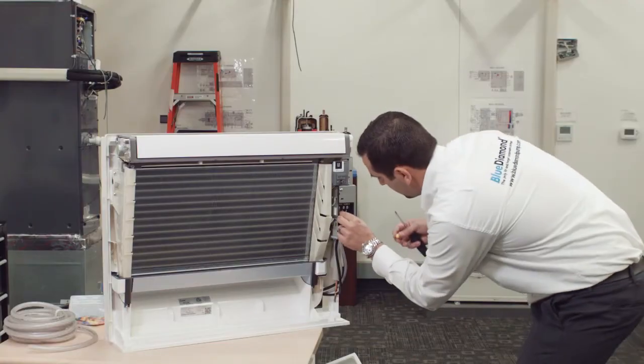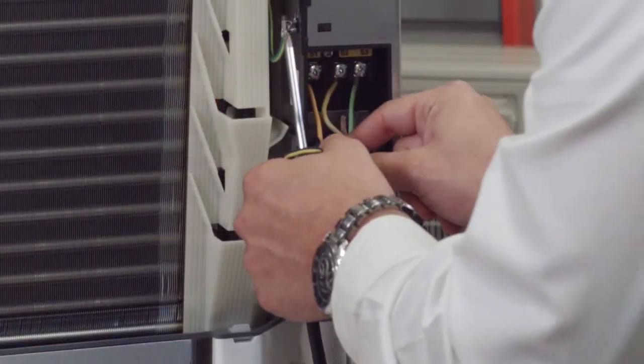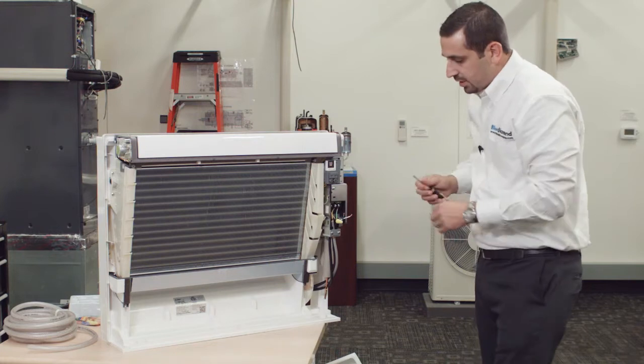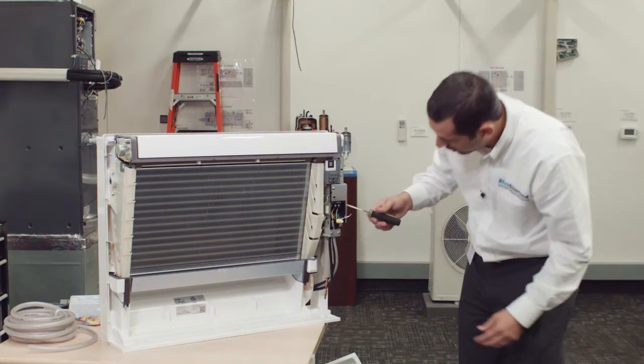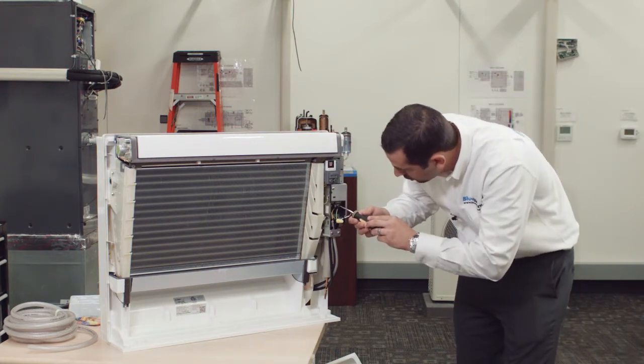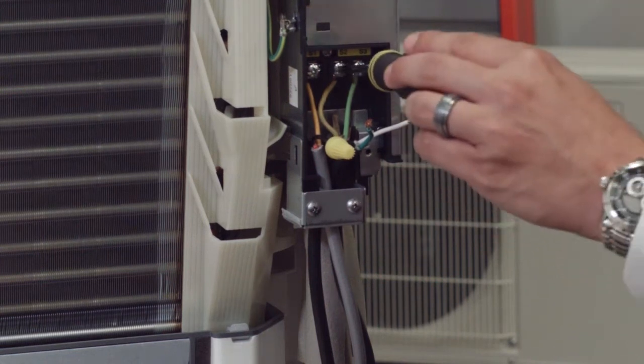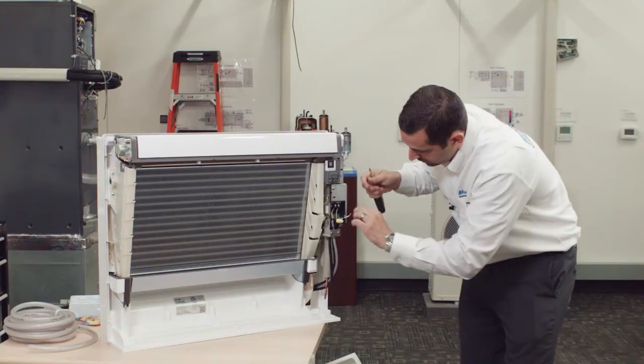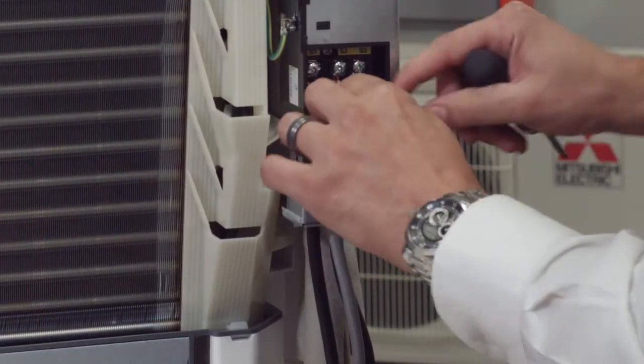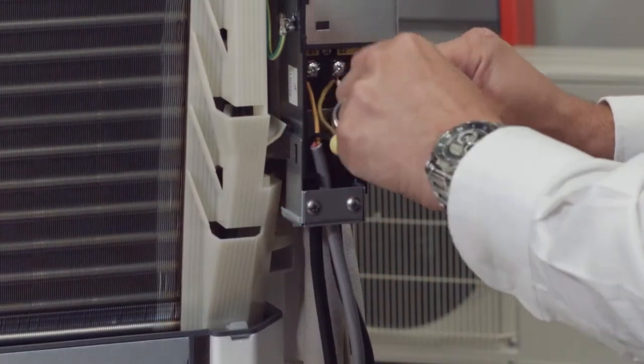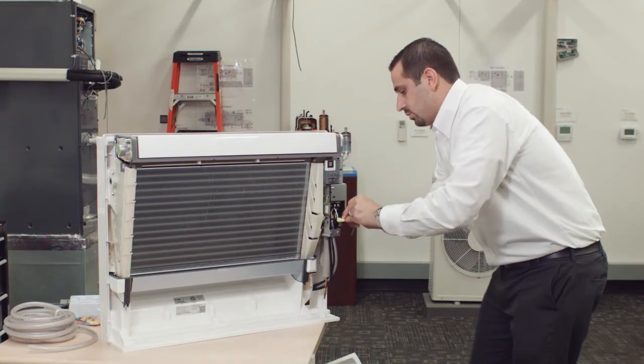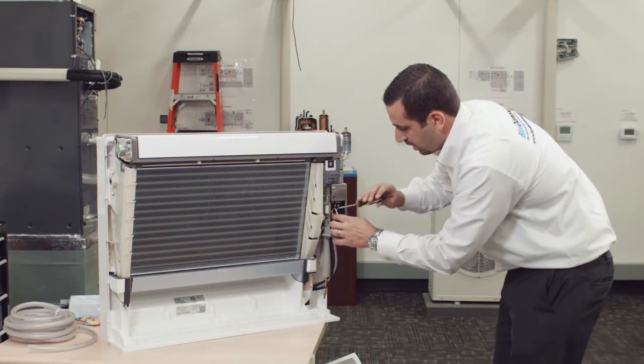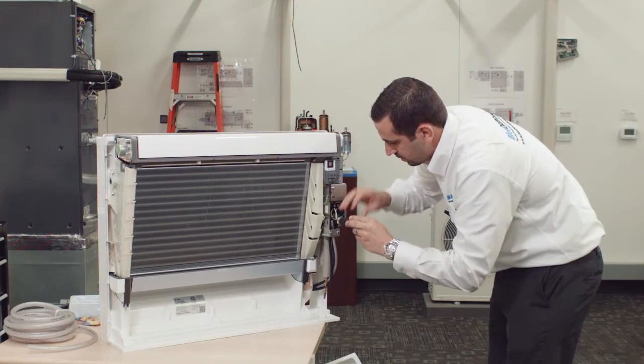Our second leg of power is going to install here on the S2 terminal. You'll notice that you're going to have your S2 wire from your condenser also installed on this terminal. And lastly, we'll take this green wire installed on this ground terminal right here.